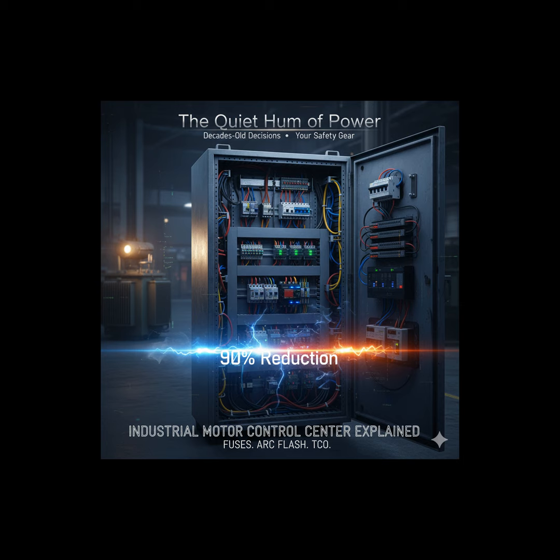Okay, so let's get inside one of these units. To understand the MCC, you have to understand the fundamental unit it contains, the combination starter. When you open one of those compartment doors, that plug-in enclosure is doing three things all at once. Three things. Okay. It's providing the actual motor starter, the short circuit protection, that's either fuses or a circuit breaker, and a disconnecting switch that allows you to safely isolate the unit from the main bus power. So we've plugged in this combination starter. What are the two core devices inside the actual motor control part? What does each one do?